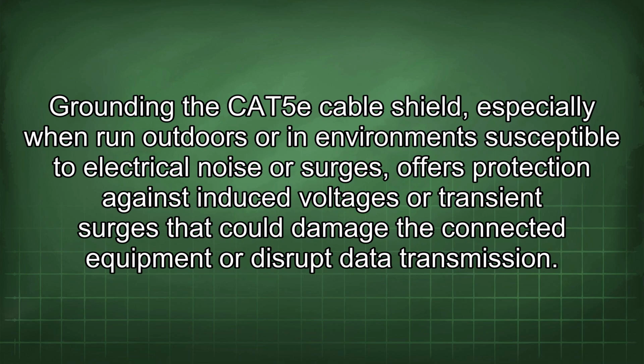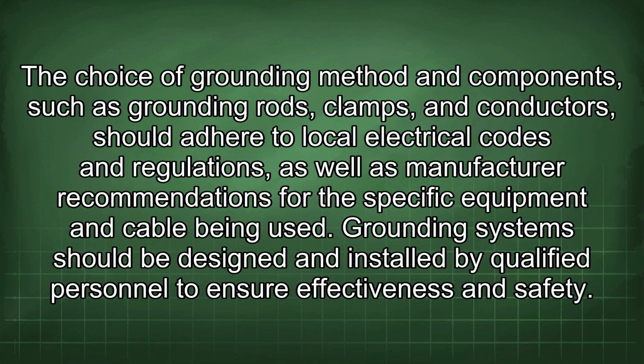Grounding the CAT5e cable shield, especially when run outdoors or in environments susceptible to electrical noise or surges, offers protection against induced voltages or transient surges that could damage the connected equipment or disrupt data transmission. The choice of grounding method and components such as grounding rods, clamps, and conductors should adhere to local electrical codes and regulations, as well as manufacturer recommendations for the specific equipment and cable being used. Grounding systems should be designed and installed by qualified personnel to ensure effectiveness and safety.